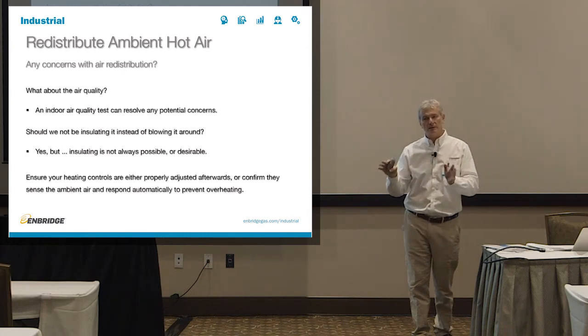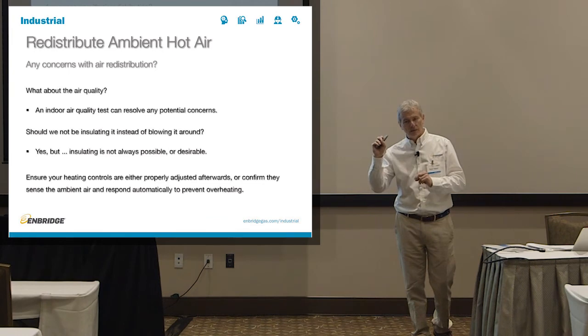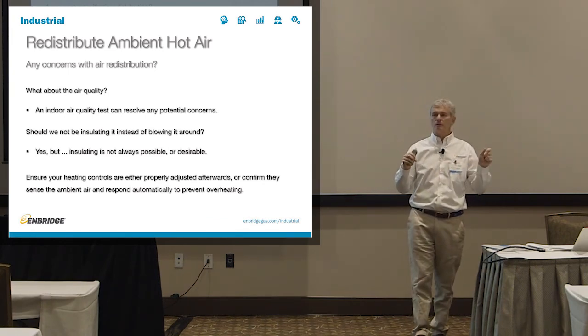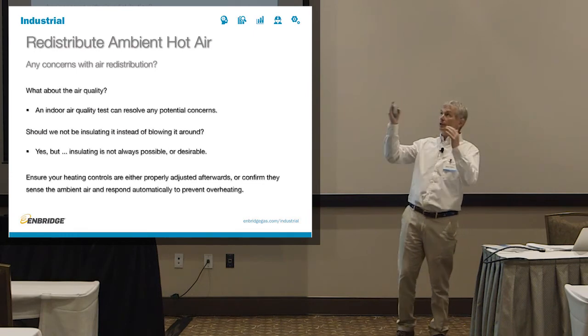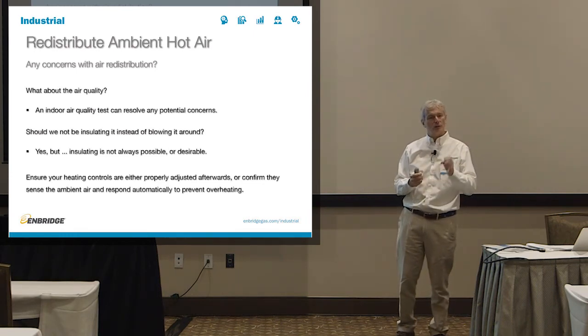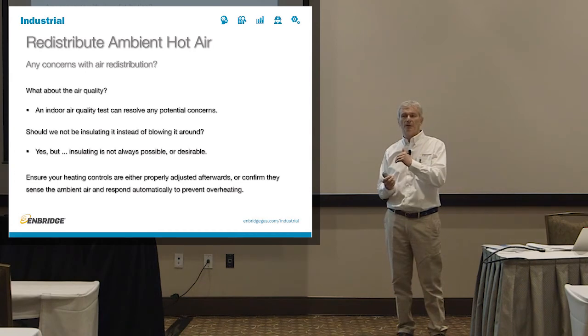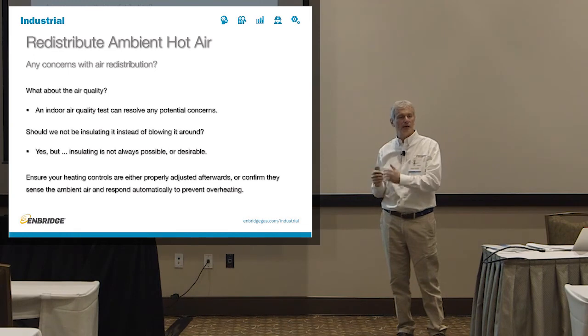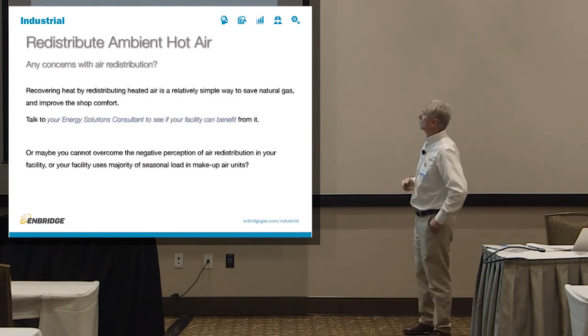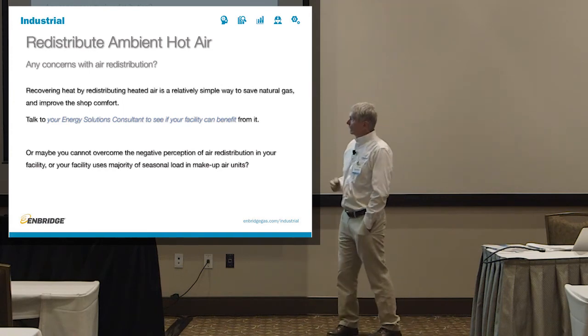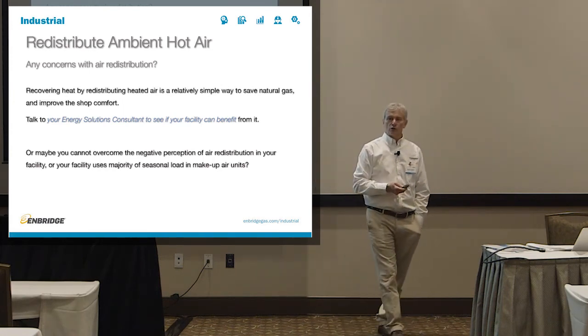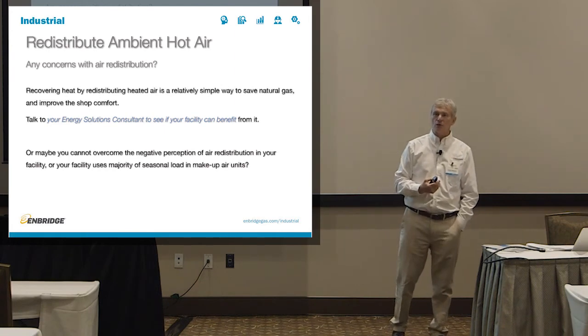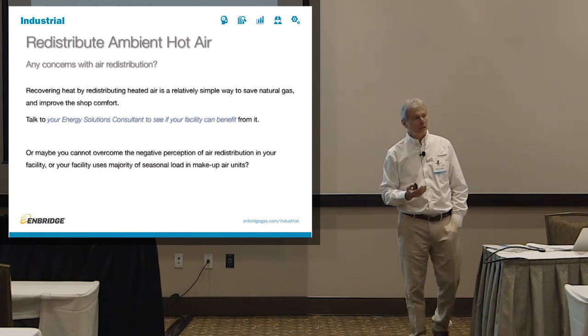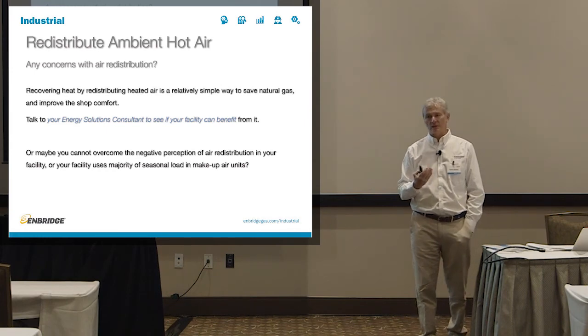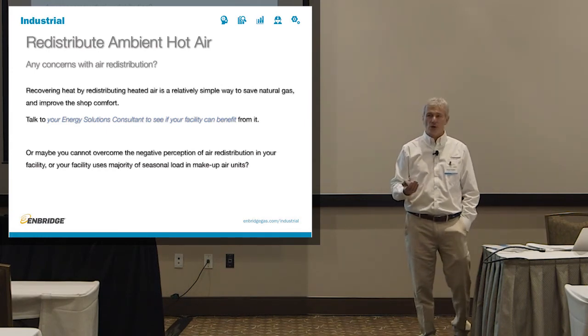On most of the industrial makeup air units, the heat that's coming out of the unit is fixed because nobody goes and adjusts it like they do here where there's people. It's just not that important. So you have a fixed amount of heat coming from your makeup air unit. So you may want to readjust that once you have an idea how much heat you're going to recover internally. Again, I would encourage you to talk to one of our energy solutions consultants, not because we know everything, but because we can do this very quickly, we can do it efficiently at no cost to you, and you will know whether there is something that is worth your time to pursue or not.